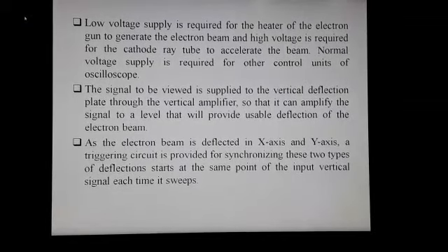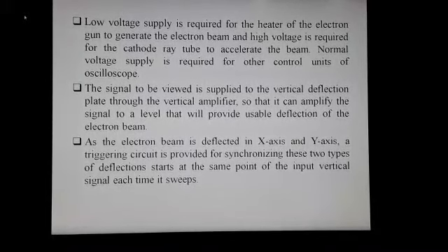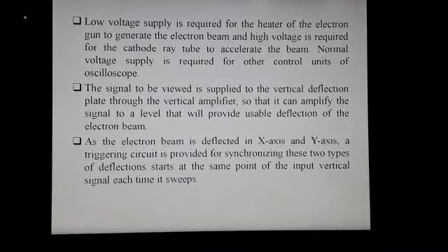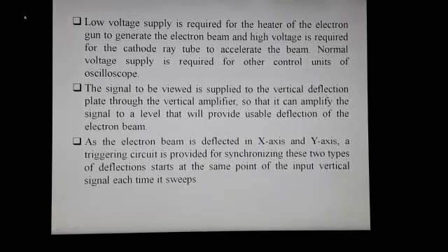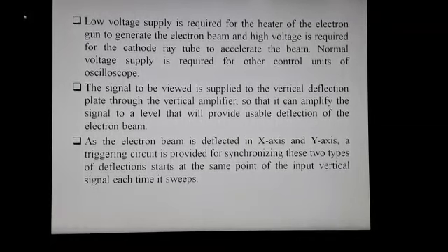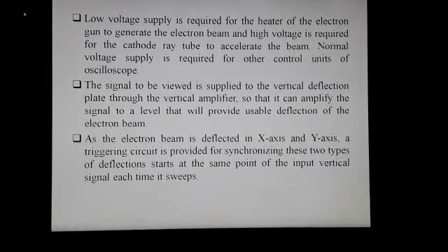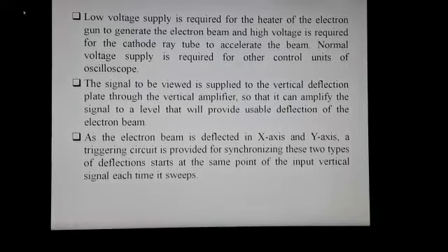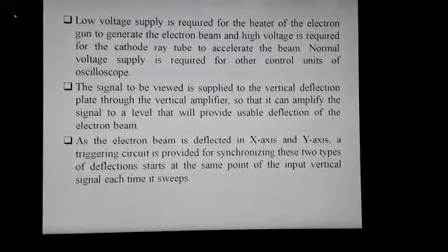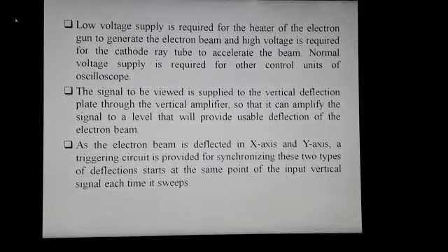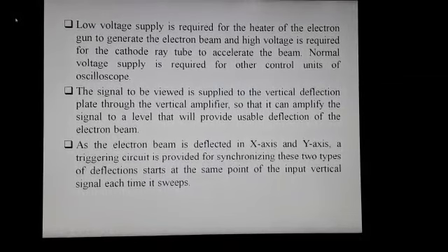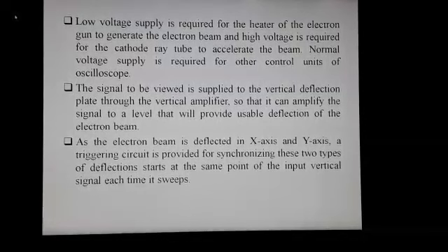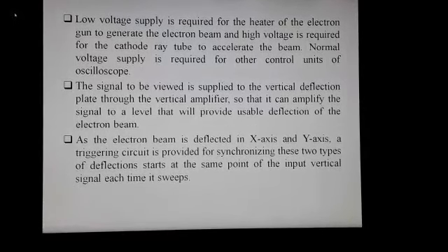Low voltage supply is required for the heater of the electron gun to generate the electron beam, and high voltage is required for the cathode ray tube to accelerate the beam. Normal voltage supply is required for other control units of the oscilloscope. The signal to be viewed is supplied to the vertical deflection plate through the vertical amplifier so that it can amplify the signal to a level that will provide usable deflection of the electron beam. A triggering circuit is provided for synchronizing the x-axis and y-axis deflections so they start at the same point of the input vertical signal each time it sweeps.